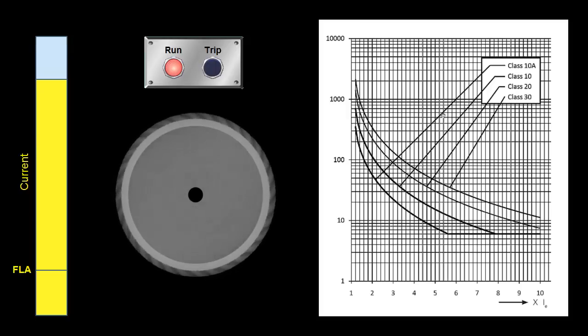So if my trip class is 10 or 10A, I'm going to run into a problem, because it's going to trip before it gets up to speed and can start pulling its nominal FLA.